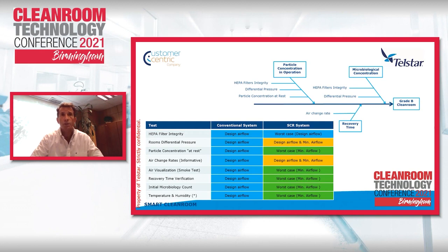Air visualization and smoke test, we will make it. I think the conclusion was that the more critical is the worst, and the worst case will be the minimum airflow in eco mode. Recovery time verification also in eco mode, initial microbial count in eco mode, and temperature and humidity also in eco mode. This obviously has to be joint work with the user quality department, and there might be some debates, but it's only a matter of fixing the scope of the qualification.